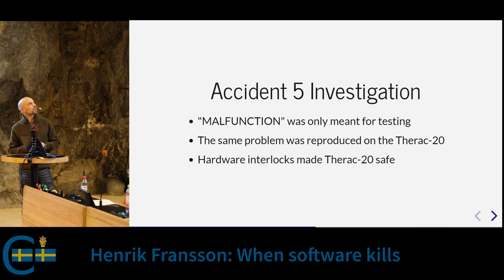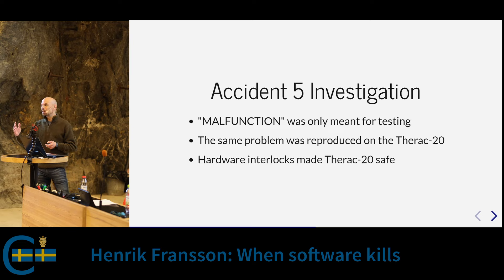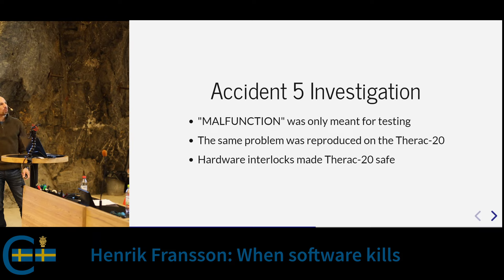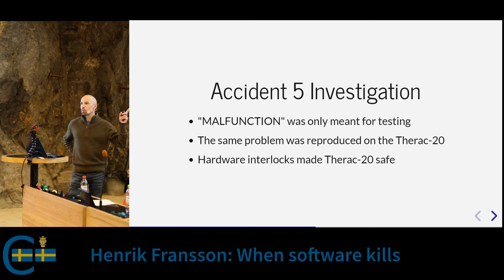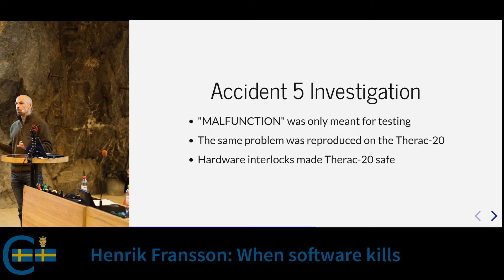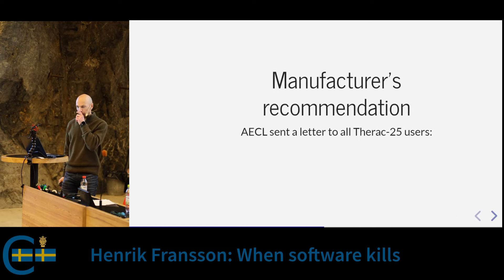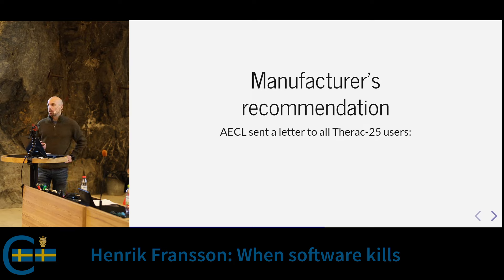In the continued investigation, the manufacturer revealed that 'Malfunction 54' was only meant for internal testing — it was never meant to appear in a real-world deployment. Forgetting debug code in production happens to all of us. They also managed to reproduce the same problem on the earlier Therac-20, but that machine had hardware interlocks so it never caused harm — it would simply refuse to start the beam. The problem was already there, but it didn't manifest because secondary hardware systems protected the patient.